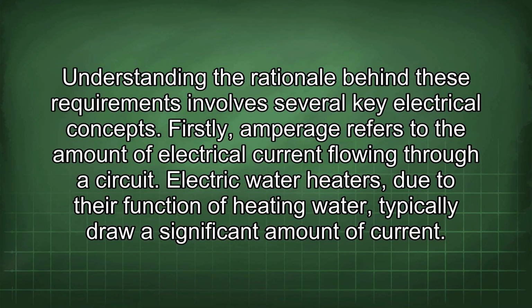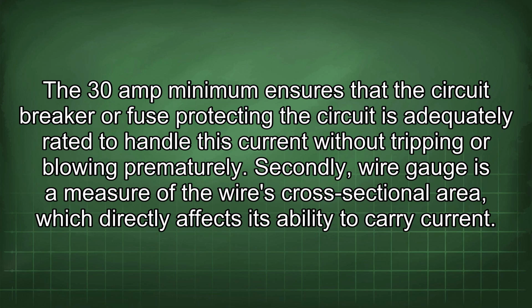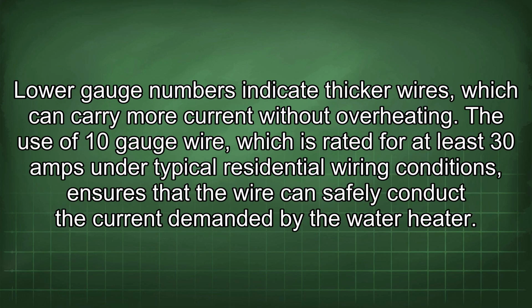Firstly, amperage refers to the amount of electrical current flowing through a circuit. Electric water heaters, due to their function of heating water, typically draw a significant amount of current. The 30-amp minimum ensures that the circuit breaker or fuse protecting the circuit is adequately rated to handle this current without tripping or blowing prematurely. Secondly, wire gauge is a measure of the wire's cross-sectional area, which directly affects its ability to carry current. Lower gauge numbers indicate thicker wires, which can carry more current without overheating. The use of 10-gauge wire, which is rated for at least 30 amps under typical residential wiring conditions, ensures that the wire can safely conduct the current demanded by the water heater.